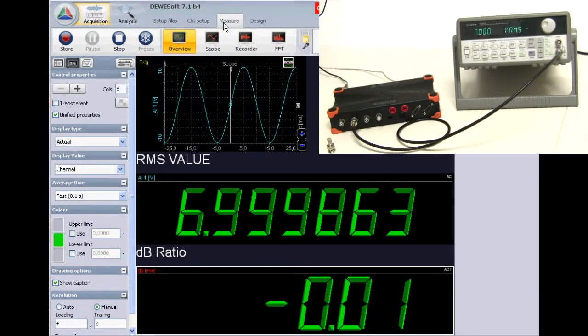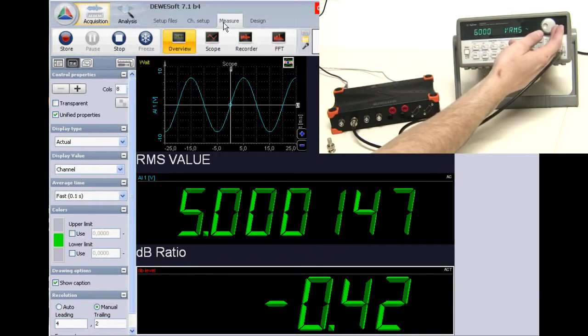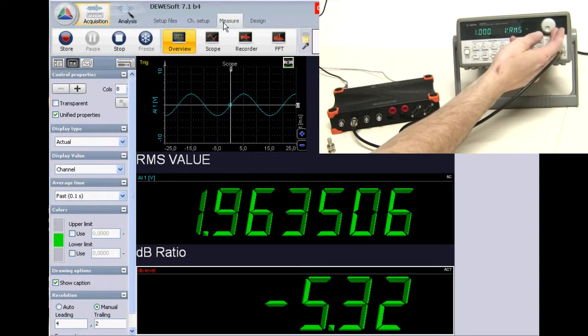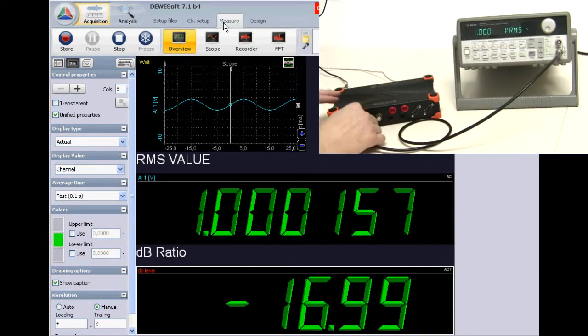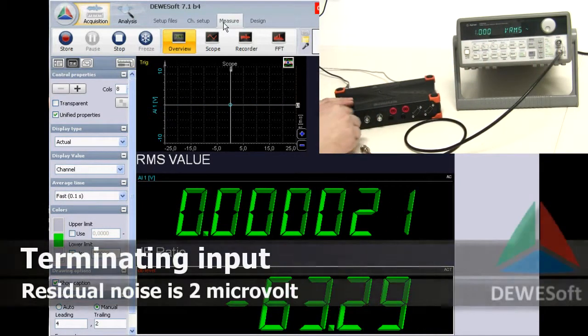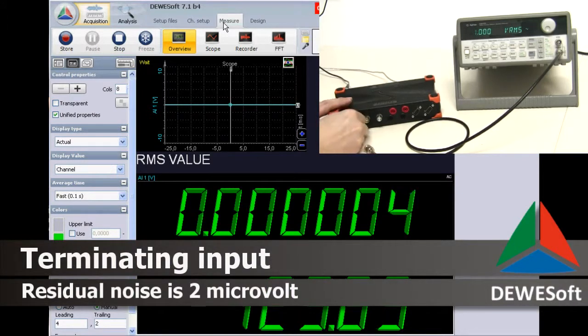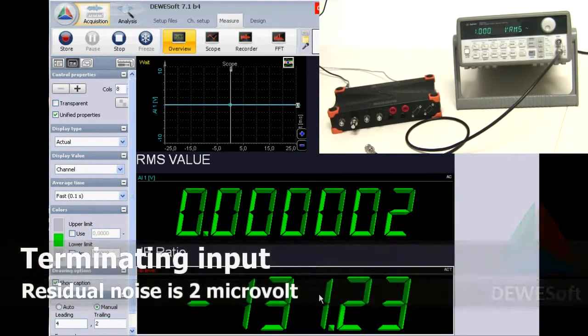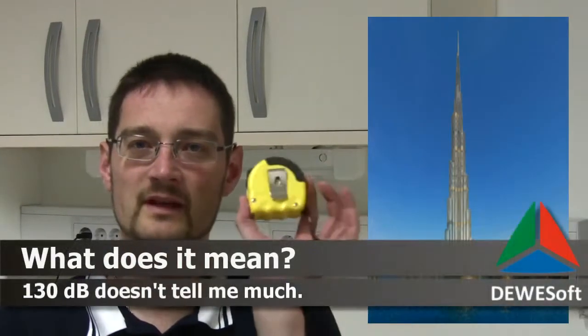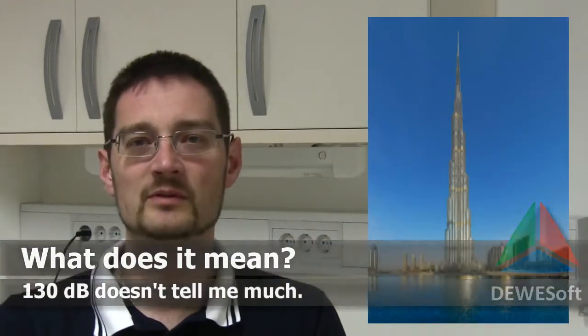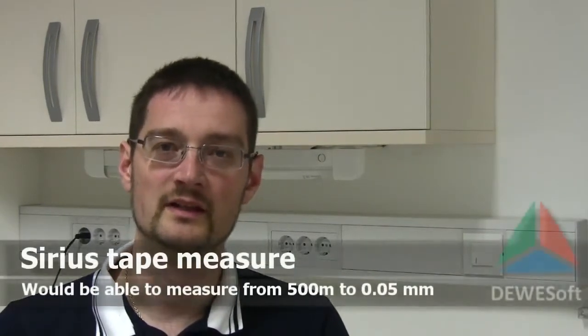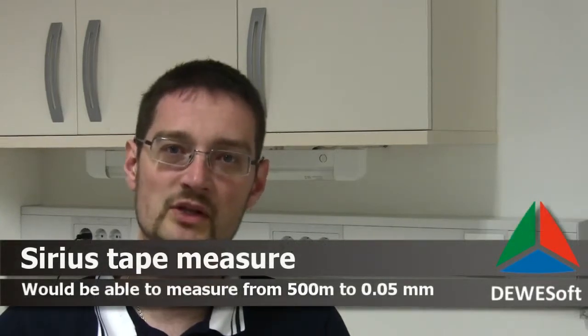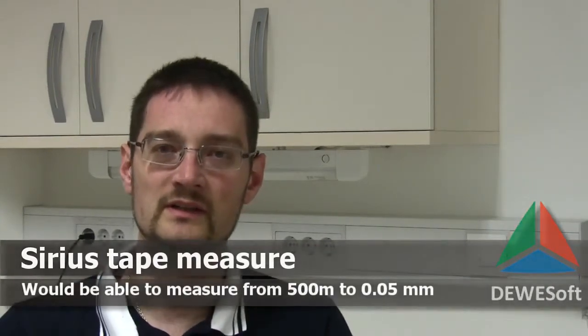With the dual-core technology, Sirius can achieve more than 130 dB signal-to-noise ratio. In other words, Sirius has more than a 1 to 2 million ratio between full scale and the noise floor. Imagine we had a tape measure able to measure buildings as high as 500 meters, and at the same time this tape measure would be able to measure distances as thin as my hair.